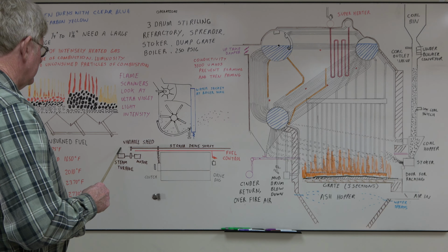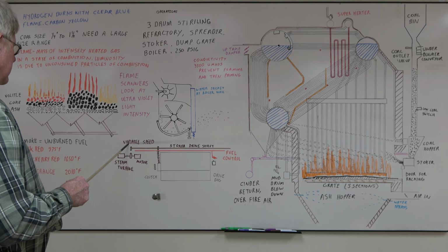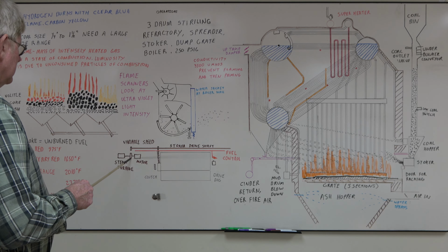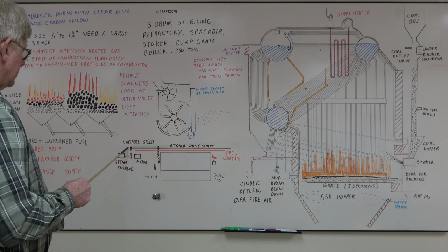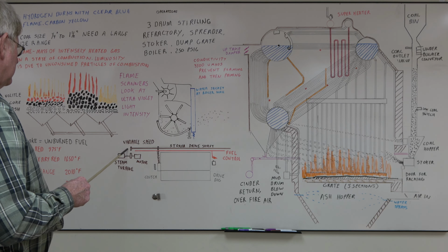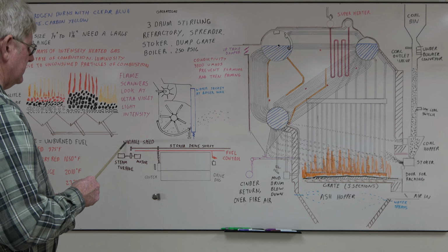Your shaft was a variable speed. You had a steam turbine for backup to an overrunning clutch. Then you had a motor. There's normal drive, then a variable speed clutch. You could crank the clutch in so it spread it out, or crank it out so it would narrow it, so you could change your speed on your shaft.